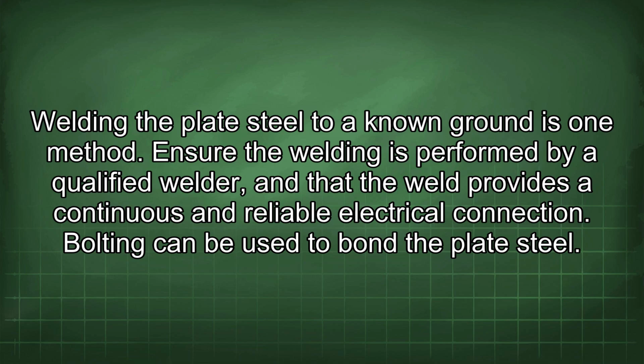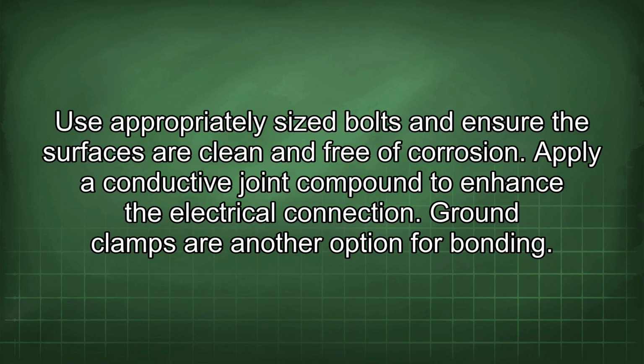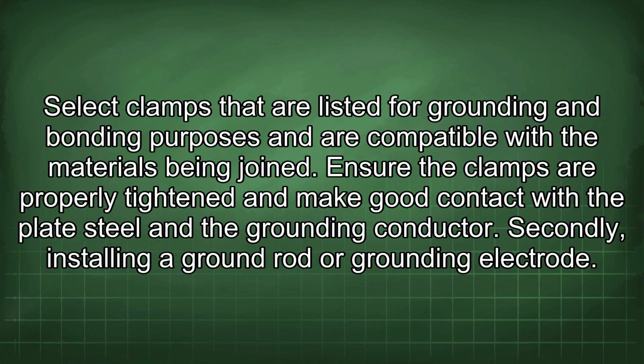Bolting can be used to bond the plate steel. Use appropriately sized bolts and ensure the surfaces are clean and free of corrosion. Apply a conductive joint compound to enhance the electrical connection. Clamps are another option for bonding. Select clamps that are listed for grounding and bonding purposes and are compatible with the materials being joined. Ensure the clamps are properly tightened and make good contact with the plate steel and the grounding conductor.